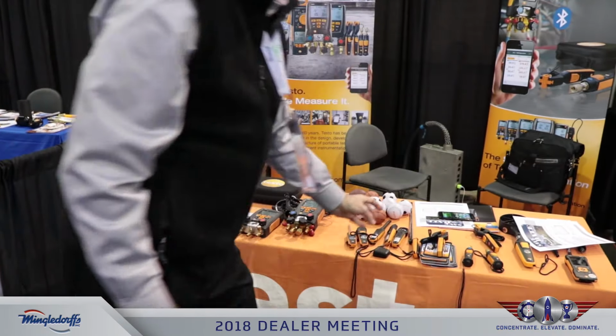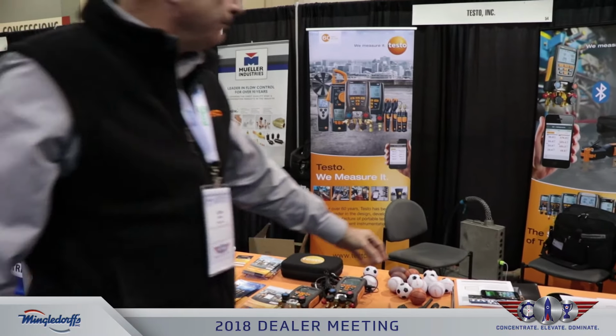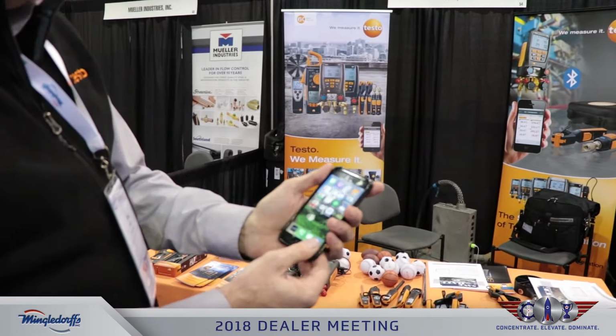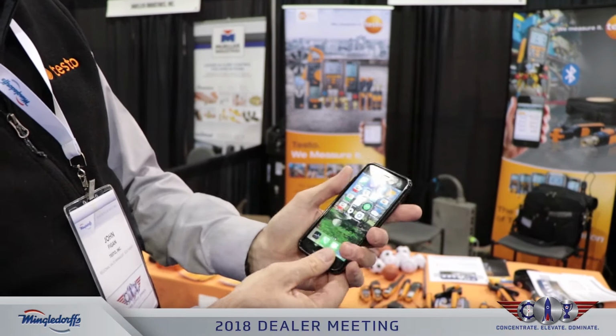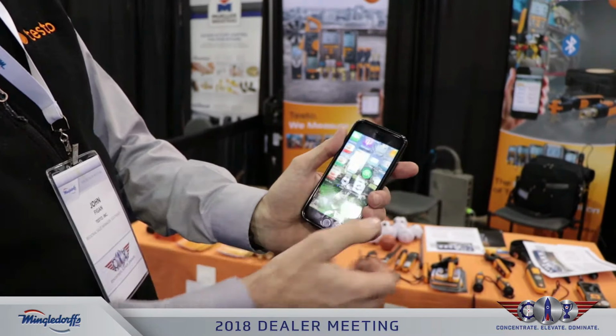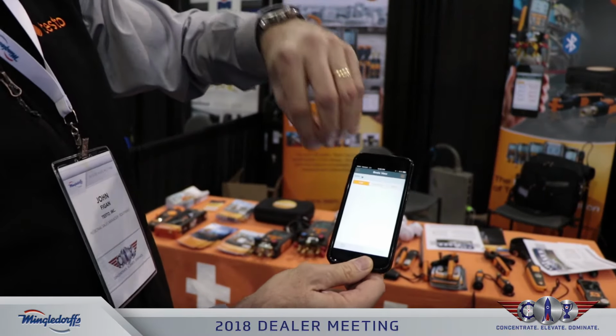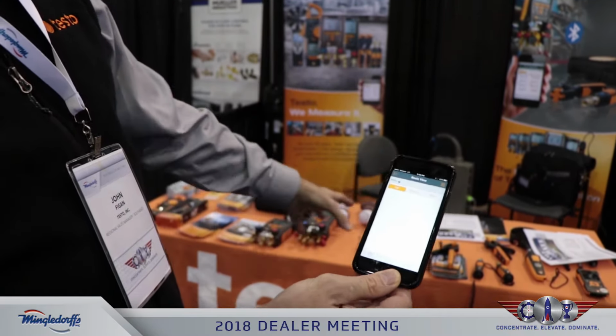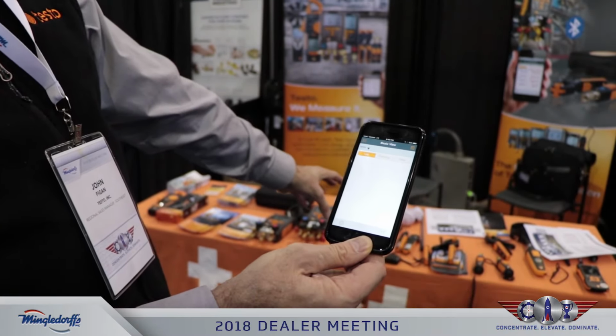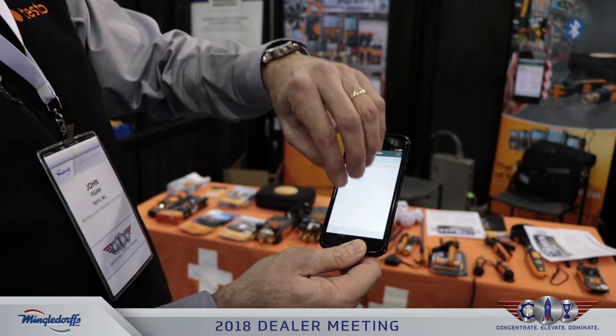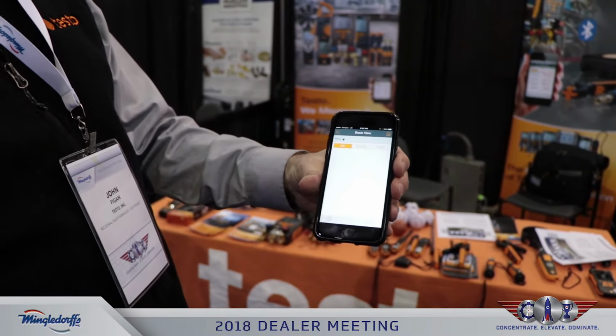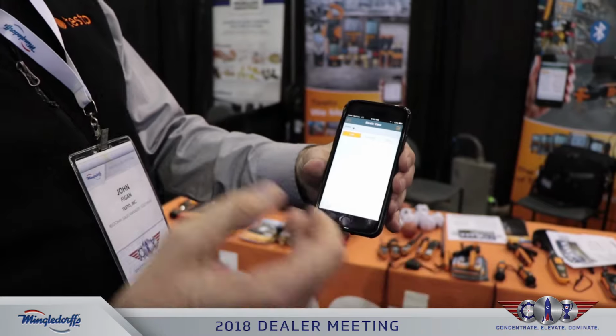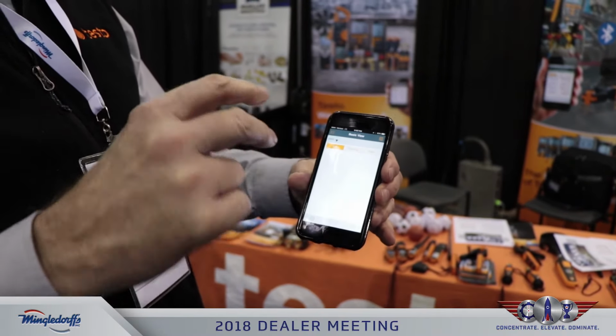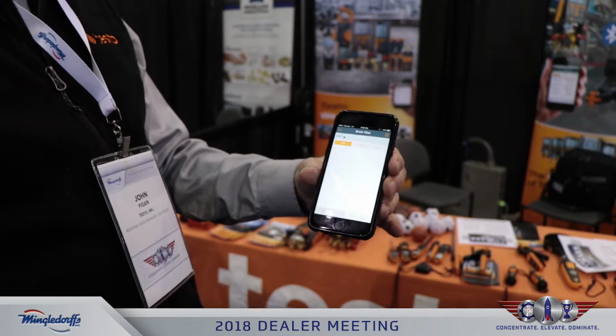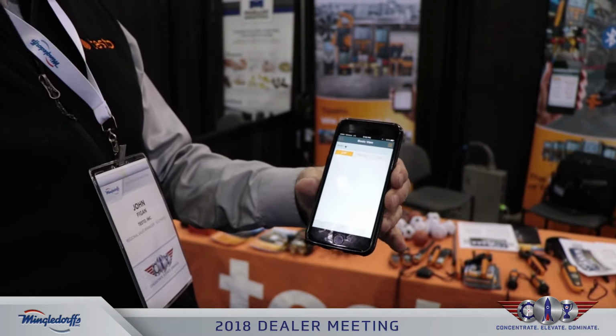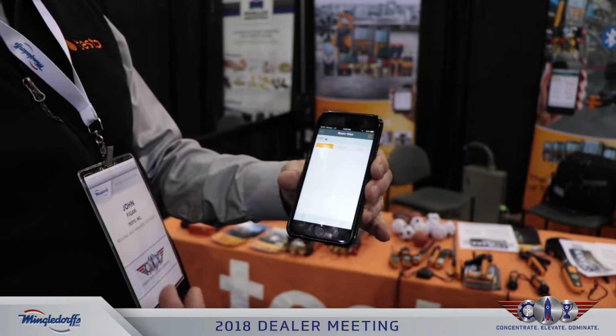And what we're able to do is use our cell phone. We're able to select an app, which is a free app from Testo, and all those probes communicate to this app, so that we are taking all the measurements from those probes. Probes are doing the measurement. They're transferring the readings to your iPad or your iPhone or your Android, and we're able to not only measure what those probes are, but we start making some calculations. We calculate superheat, subcooling. We can calculate the capacity of a system if you're using certain types of probes.